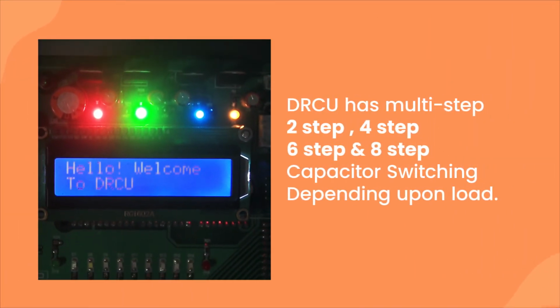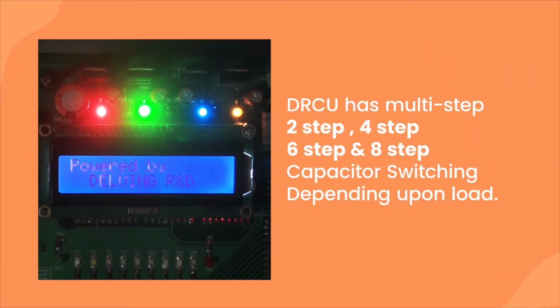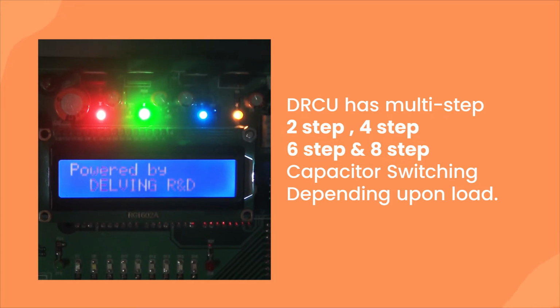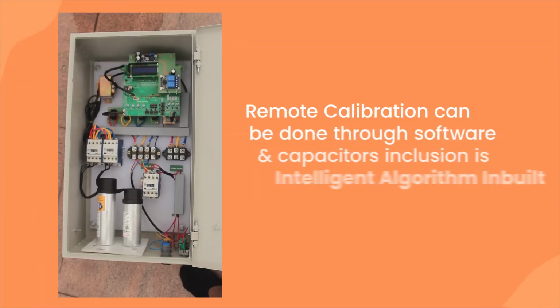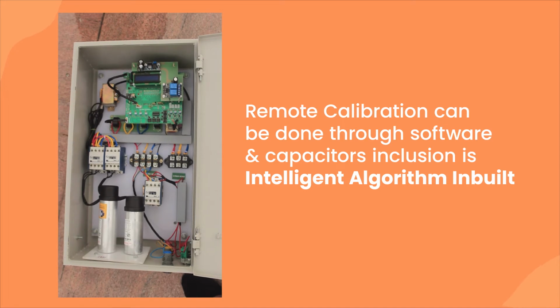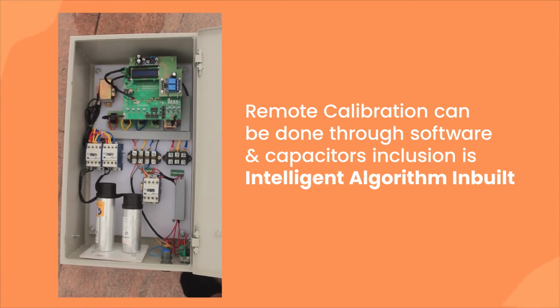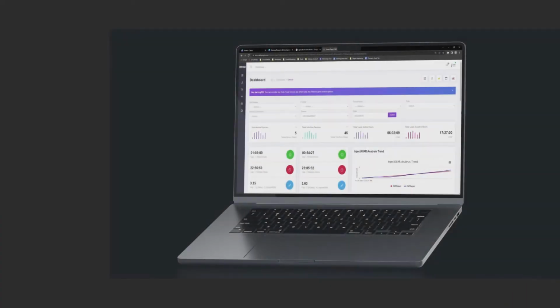DRCU has multi-step, 2-step, 4-step, 6-step, and 8-step capacitor switching depending upon load. Remote calibration can be done through software, and capacitor inclusion is based on an intelligent inbuilt algorithm.